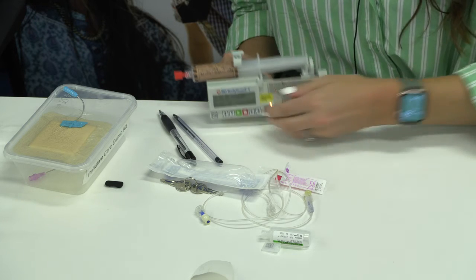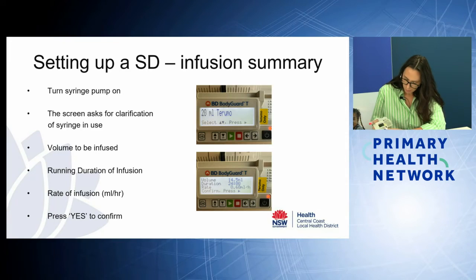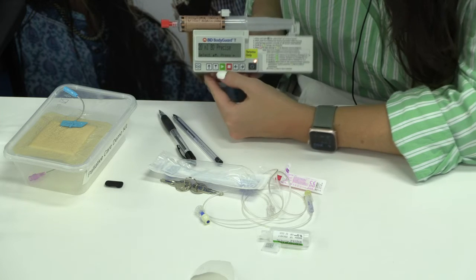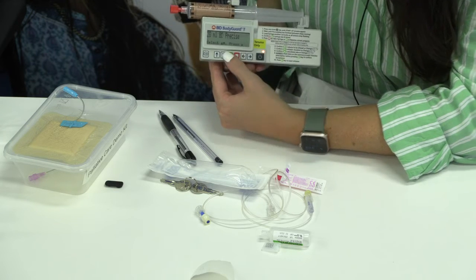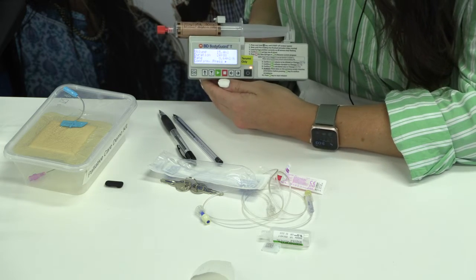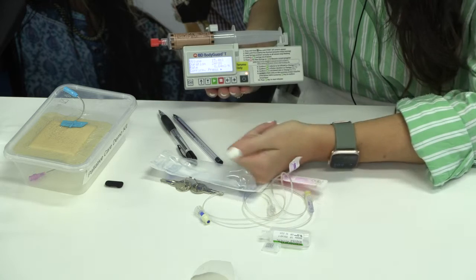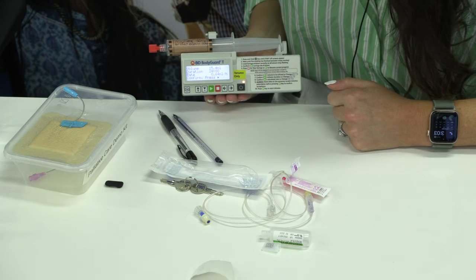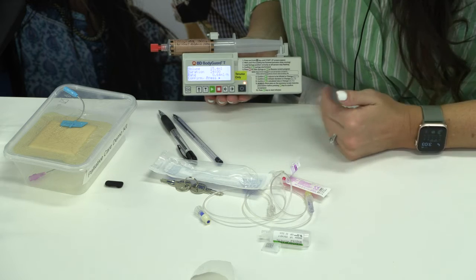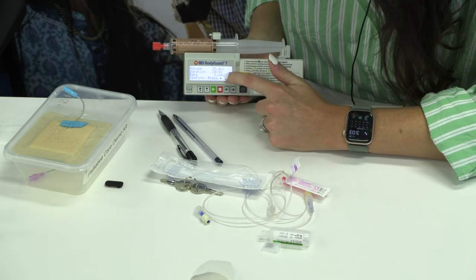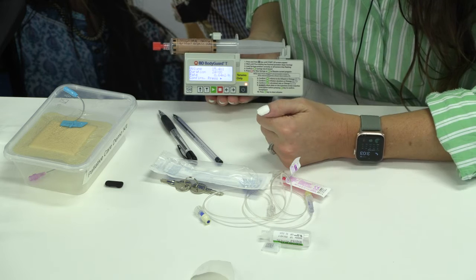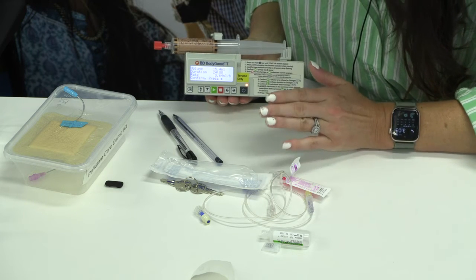between the prongs. So we've turned it on, we clarify that we've got the correct syringe, and we say yes, which then gives you the instructions. If it's not the correct syringe, you go up and down, but try and use the same syringe within your facility, and it tells you to press this arrow to confirm you have the correct one. We've pressed that. It wants to confirm the volume, the duration, and the rate. As I mentioned before, if you've got about 15 mils within, it's around 0.63, 0.64 of a mil per hour. So it will work that out perfectly for you.